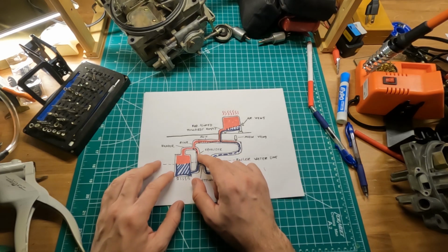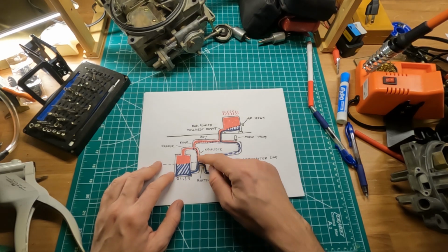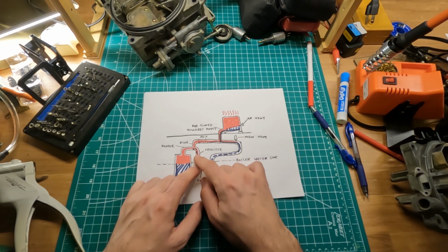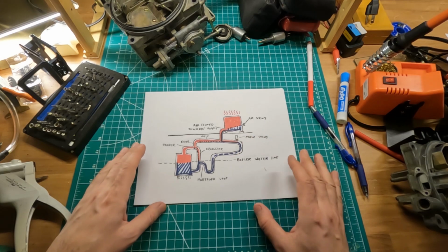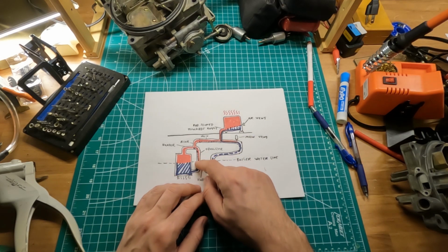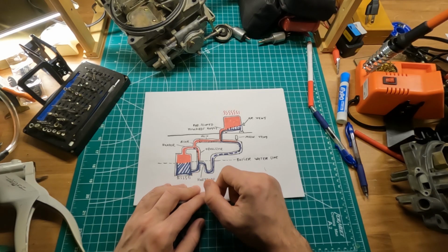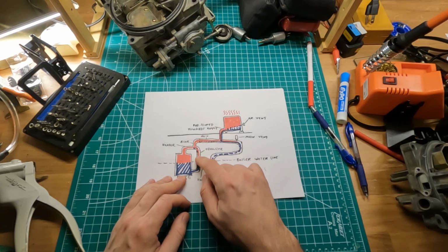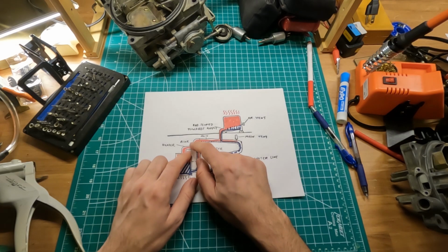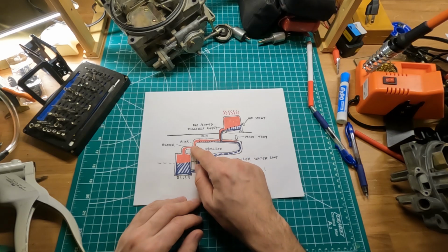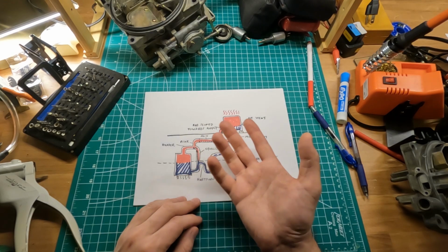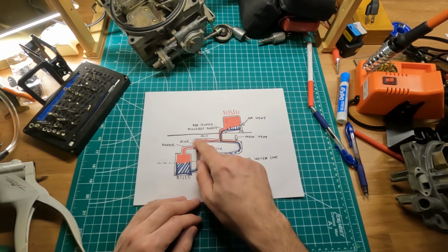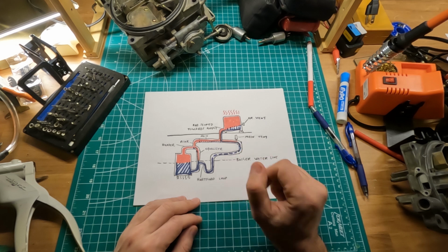The equalizer in theory is meant to equalize the pressure between the outlet and inlet. There are some theories that it actually doesn't do that much. The main function of the equalizer in a residential steam heat system is to allow the condensate to return safely back into the boiler. But for now, that's the name of that extra pipe extending out of the header at the end of it. It's called the equalizer. Somewhere along the header, we have another pipe going up, and it's called the riser. By definition, the function of a riser is to allow the steam to rise up and go farther into our main pipe, which is this one right here.